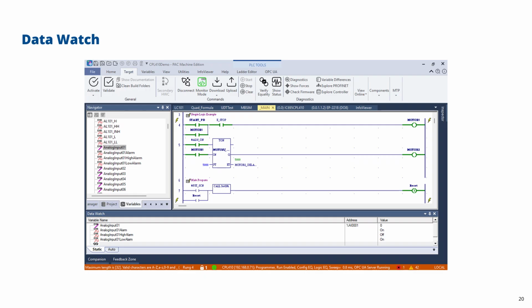And in terms of controlling them, if you want to change a value, you go over to the right hand side here, click in the value area, and you can enter the new value, and then it will write that new value to the PLC. Now the only restriction there is the value can only be written if you've actually got write access. It might be that the PLC itself is overwriting some of these values, so you can't write everything. So you also have the option to right click and force discrete values. The way that works is it overrides the actual value in the PLC with the value that you forced it to. So the PLC value will no longer take effect. It will actually have whatever your force value is.